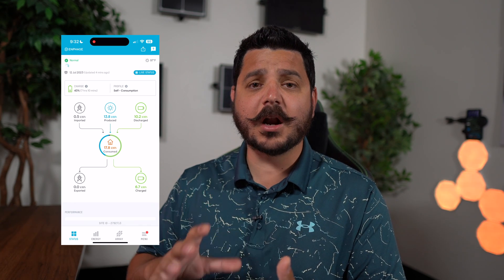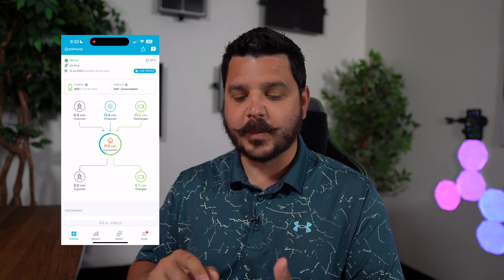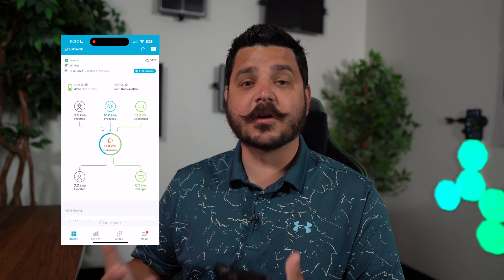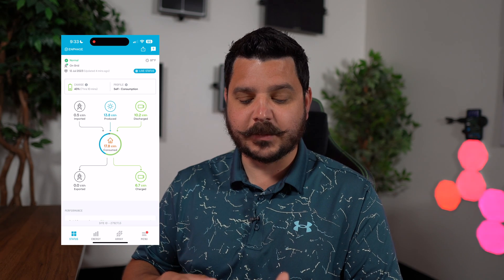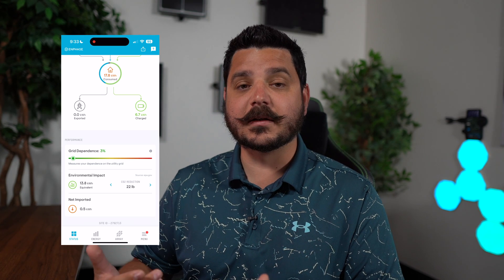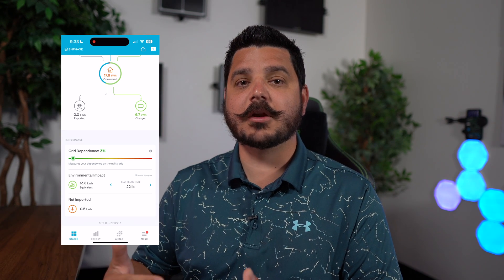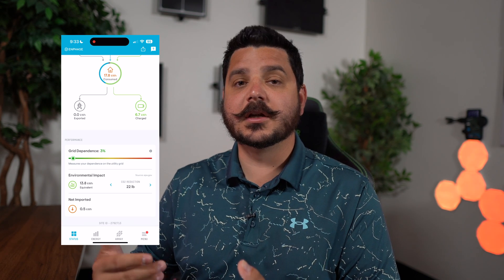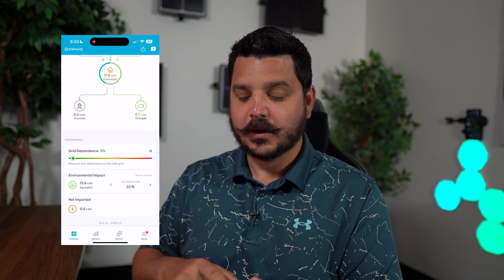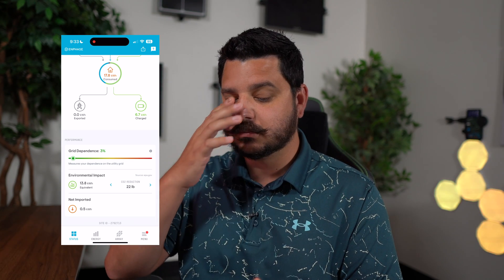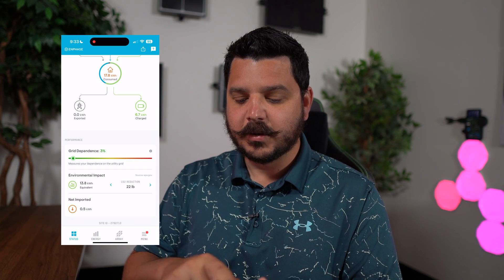You can click on Live Status, though if you have older microinverters you may not see that button in the top right. Enphase is doing some server updates as I'm recording this, so some features aren't presently available. If you scroll down, you can see this site has a grid dependence metric — you can change it to grid independence if that's easier to understand. Dependence tells you how much of the grid you're using, so the number should be lower. Independence shows how little of the grid you're using, so the number should be higher because you're using solar and batteries. Below that it shows carbon emissions saved, trees saved, and so on.